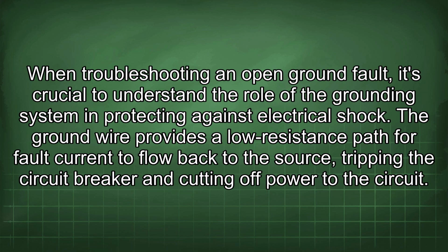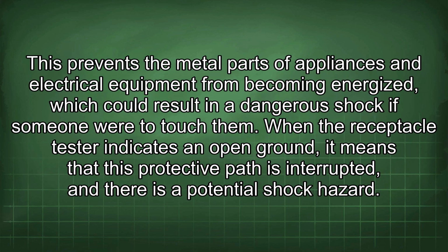When troubleshooting an open ground fault, it's crucial to understand the role of the grounding system in protecting against electrical shock. The ground wire provides a low resistance path for fault current to flow back to the source, tripping the circuit breaker and cutting off power to the circuit. This prevents the metal parts of appliances and electrical equipment from becoming energized, which could result in a dangerous shock if someone were to touch them.